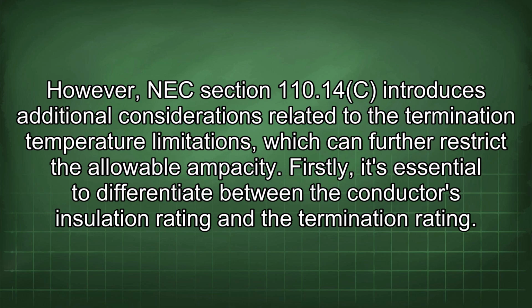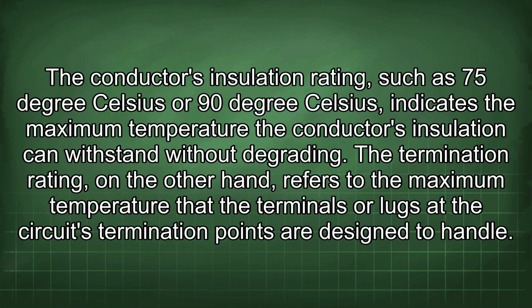allowable ampacity. Firstly, it's essential to differentiate between the conductor's insulation rating and the termination rating. The conductor's insulation rating, such as 75 degrees Celsius or 90 degrees Celsius, indicates the maximum temperature the conductor's insulation can withstand without degrading. The termination rating, on the other hand, refers to the maximum temperature that the terminals or lugs at the circuit's termination points are designed to handle.